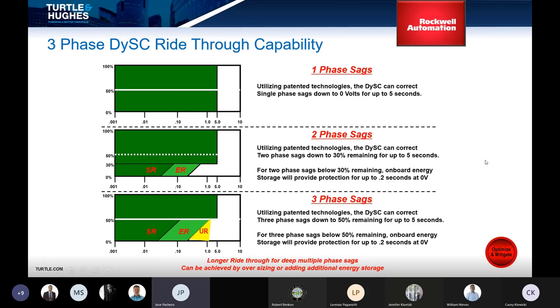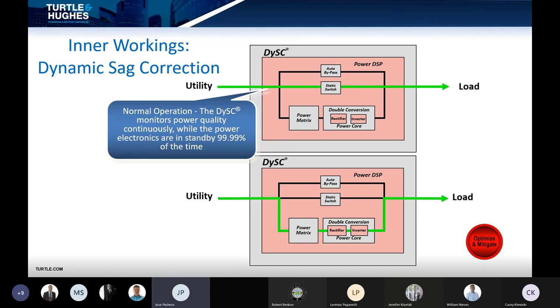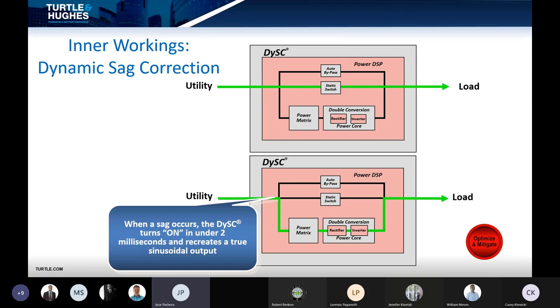There are different flavors of DySC. For single-phase sags, it can ride through up to five seconds. As you add more phases, up to three phases, and if you want to mitigate longer power events, you need to consider either an extended range or ultra range option. During normal operation, DySC monitors power quality continuously while the power electronics are on standby. When an event occurs, it corrects it in under two milliseconds. The average facility sees 20 to 30 events per year, mostly well under a second, with power electronics activated for approximately 30 seconds a year total — which is why the product is so efficient.